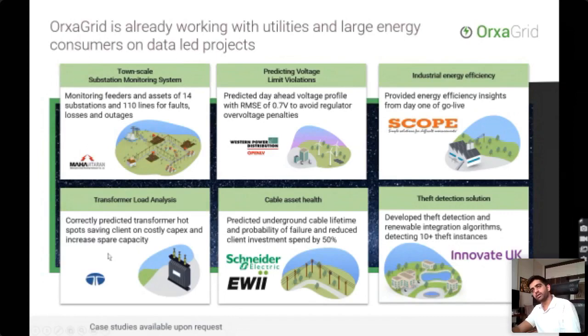We also did a similar project for Tata, doing transformer load analysis for their solar generation plant in Bikaner, where we monitored their step-up transformers after generation and before connection to the grid. We looked at transformer load profiles to understand whether all transformers were generating evenly, or whether certain transformers were not behaving per standard methods, and provided monthly reports to the customer and grid operator on what changes could be done. We correctly predicted transformer hotspot temperatures, saving the client costly capex and increasing spare capacity on the network. That was the Tata project.